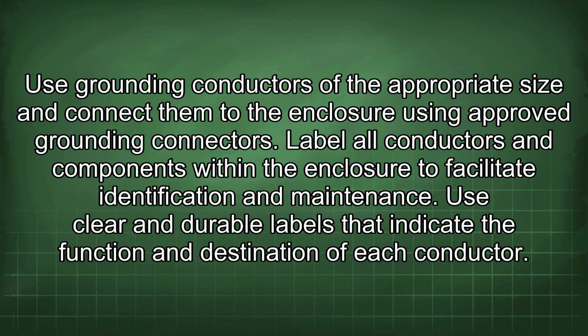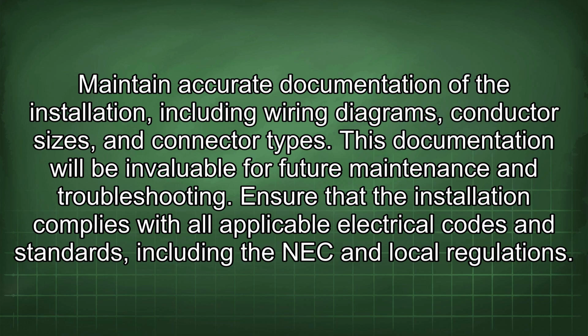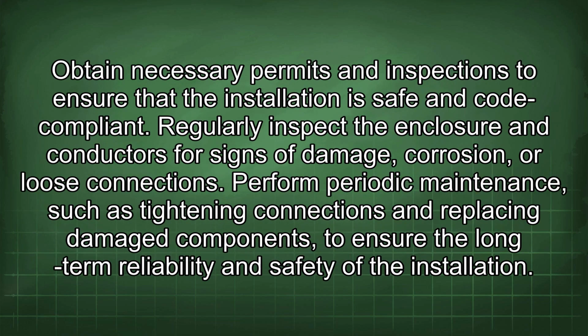Use clear and durable labels that indicate the function and destination of each conductor. Maintain accurate documentation of the installation, including wiring diagrams, conductor sizes, and connector types. This documentation will be invaluable for future maintenance and troubleshooting. Ensure that the installation complies with all applicable electrical codes and standards, including the NEC and local regulations. Obtain necessary permits and inspections to ensure that the installation is safe and code compliant.